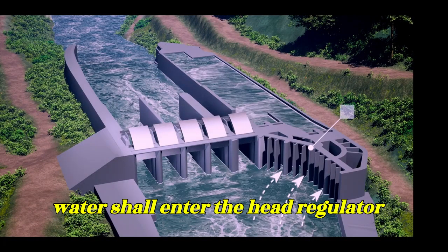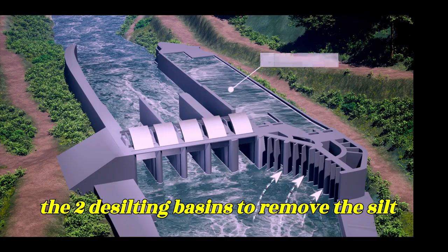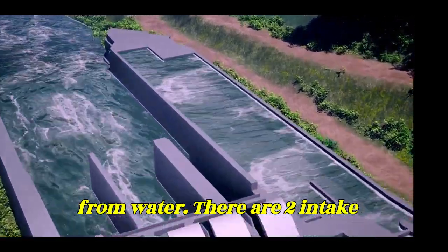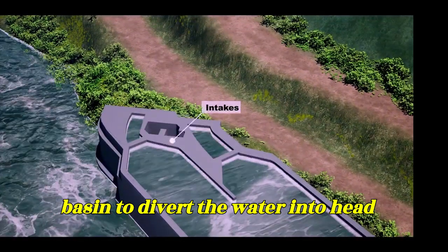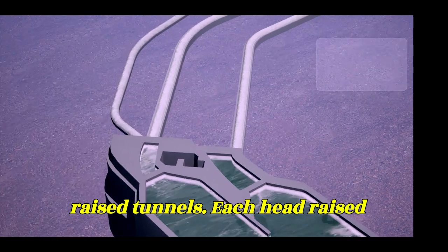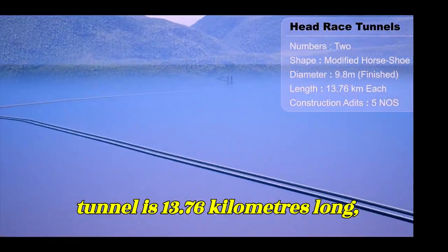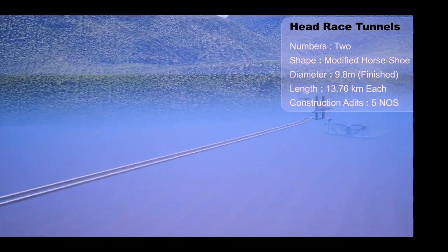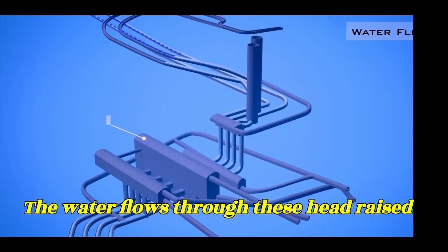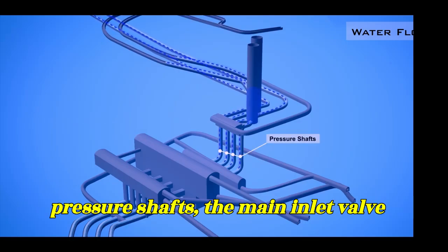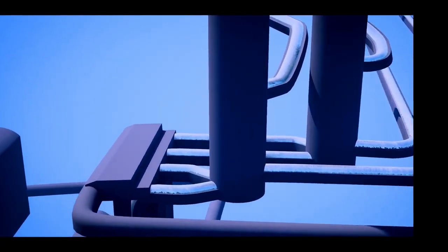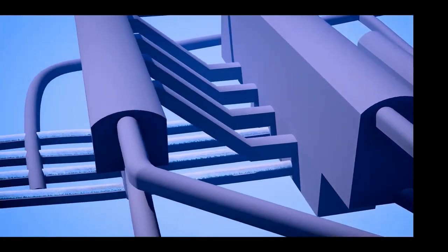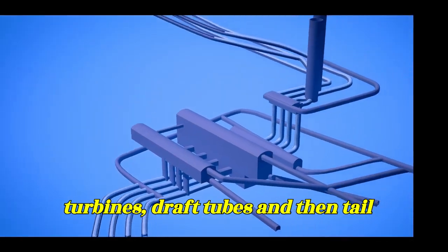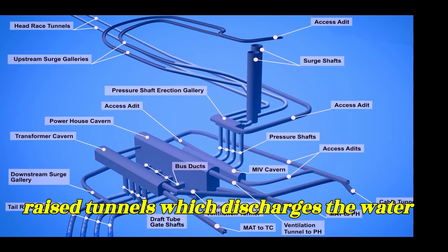Water shall enter the head regulator structure, which will lead the water to the 2 desilting basins to remove the silt from water. There are 2 intake structures downstream of the desilting basin to divert the water into head race tunnels. Each head race tunnel is 13.76 kilometers long, modified horseshoe shaped. The water flows through these head race tunnels to the powerhouse through the pressure shafts and the main inlet valve cavern. The water then passes through the turbines, draft tubes and then tail race tunnels, which discharge the water back into the river.